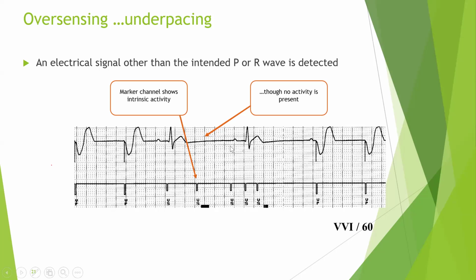Again, you can see on the surface ECG there is nothing, and the device is saying V-sense, meaning that it senses ventricular activity while there is no ventricular activity. After that, there is a true QRS, and the device says V-sense, but it even shows us another sensing event after the T wave. So this indicates that the lead is really oversensing. The most common cause of oversensing is interference. There is some interference from the environment, like an electromagnetic field, or diathermy, if the patient is under operation, for example.